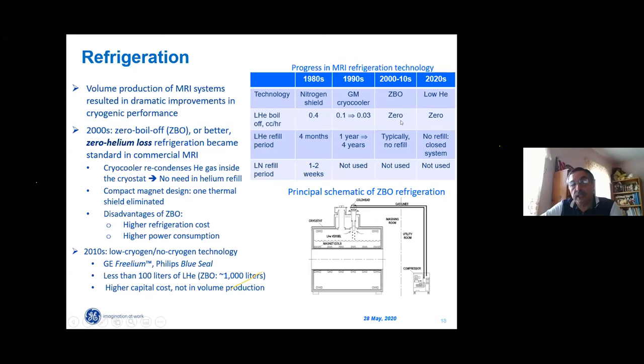It is not guaranteed, but let's say 90% of installed MRI magnets don't require a refill while they're installed on site. And the latest advances: the Blue Seal from Philips, the Freelium technology, low cryogen or no cryogen at all. Philips advertises that they have only 7 liters of liquid helium in the system. So soon we expect commercialization of this Freelium Blue Seal technology. It is still not in volume production, but I know that a Philips plant for volume production is being built close to where I live.